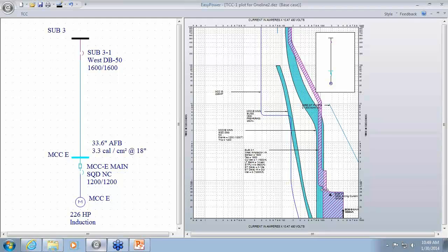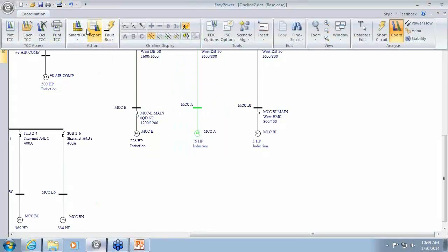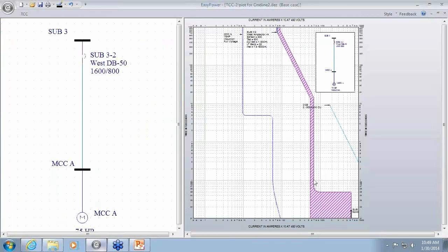So, but you also have to consider what effects reducing that instantaneous has on the rest of your circuit, because you are reducing your reliability, and that's where we talk about those special cases. So that's one case. I'm just going to show this one, even though we won't be changing any settings because the hazard is small. But this is an LI function.